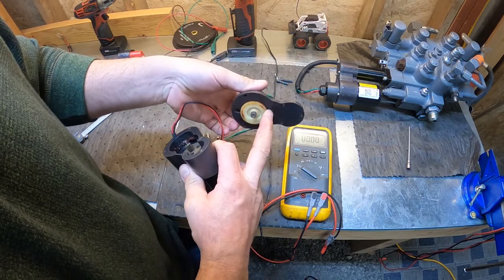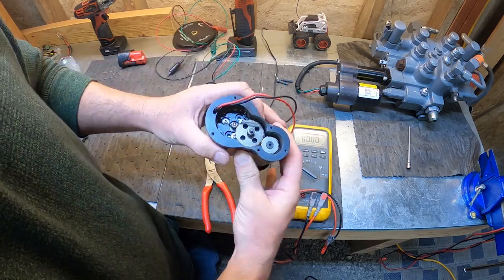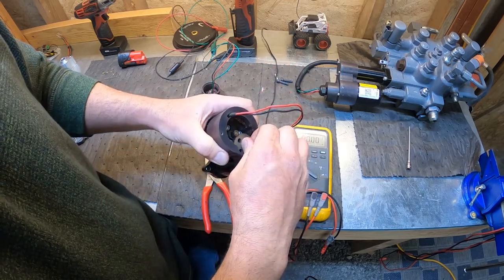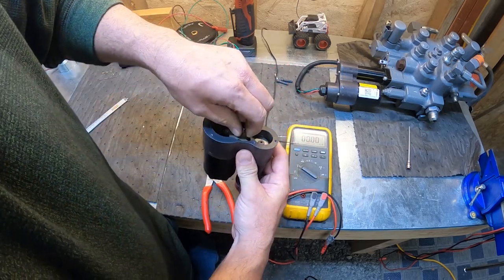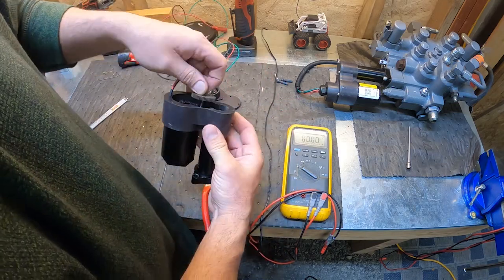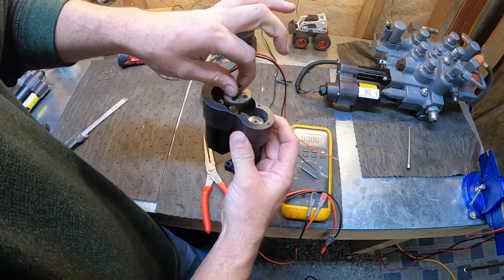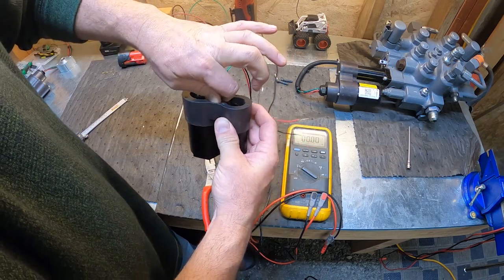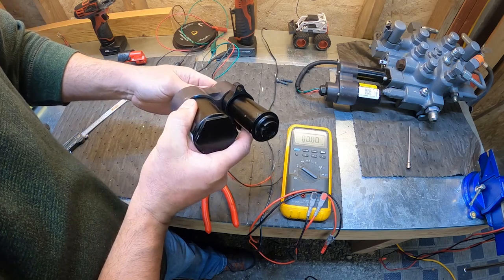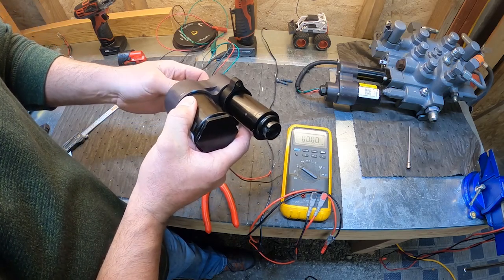Okay, we take the top off, gear for Hall effect sensor. This is where I was talking about. We went to a gearbox now. I can turn it by hand anyways. Turn the gearbox by hand. Oop. That center gear does come out. You can see we can run our piston out of our actuator.